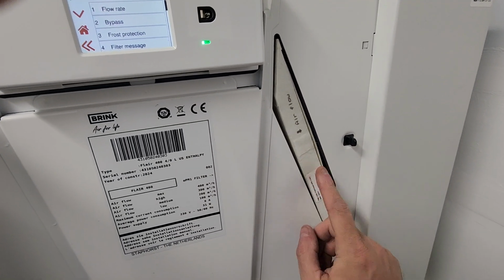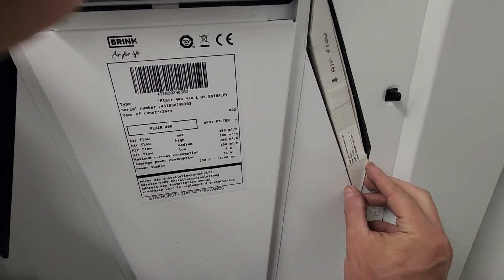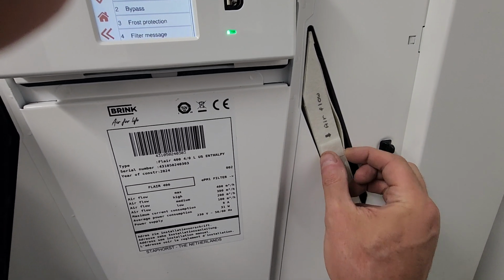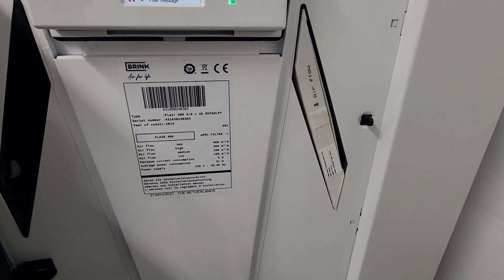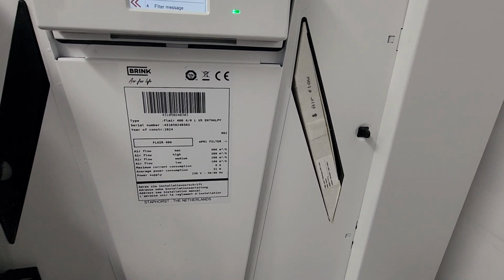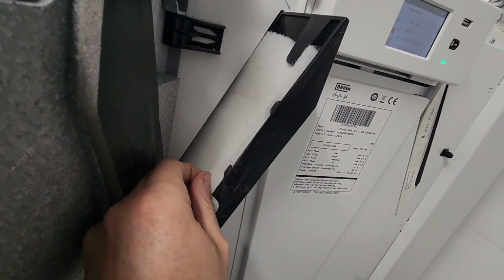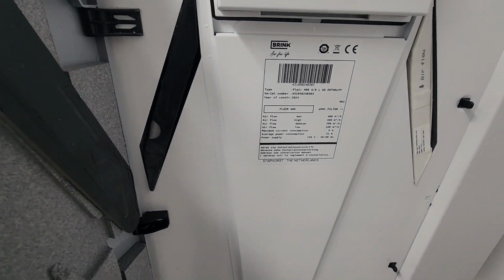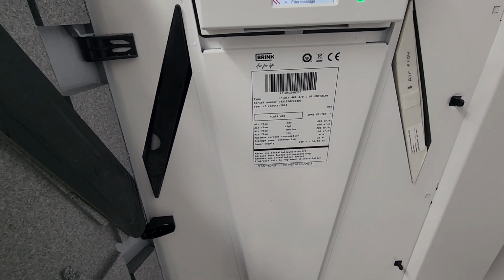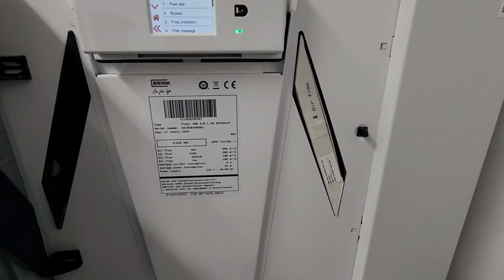It comes with 2 filters. This filter is for the fresh air coming in from outside. What happens with this air filter is that it's, I believe, like a MERV 8. So it's going to do mostly particulates from the outside, pollen, smoke, anything like that, it takes care of. And then on the other side, it's just kind of a more flimsy filter, but this is just to protect the core and the motor from all the dust inside the house, and this is washable. While this one's not washable, you have to replace this bad boy.